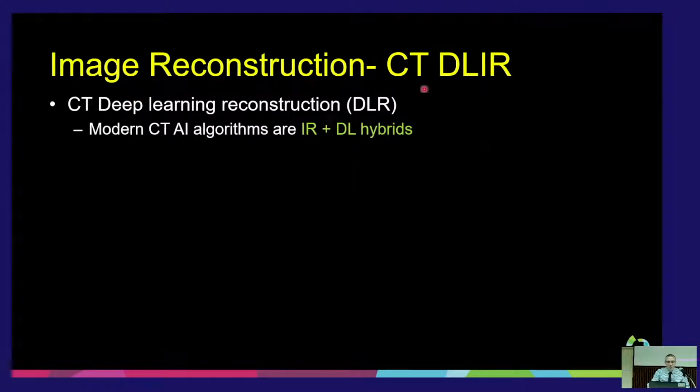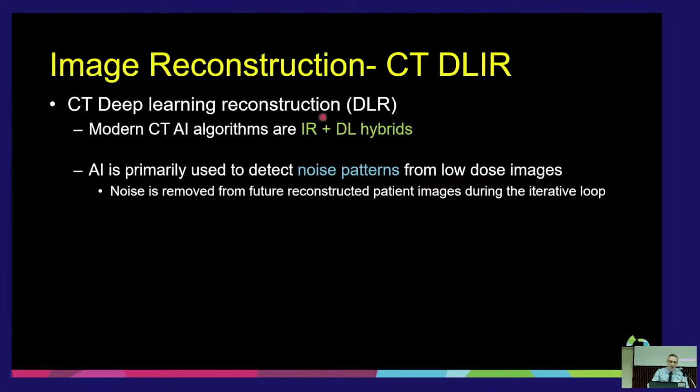So with technology, we have now introduced deep learning algorithms to try to improve upon the removal of noise but preserve the edges of structures. So deep learning algorithms have been inserted into the iterative process. So you're still iterating, but instead of using a regularization function to kind of go around cleaning up, like a little, what are those called, Roombas that just float around all your house picking up trash, instead of trying to go around the image cleaning up the noise, now what we're doing is we're teaching the machine to recognize what is noise and what is a structure, anatomy.